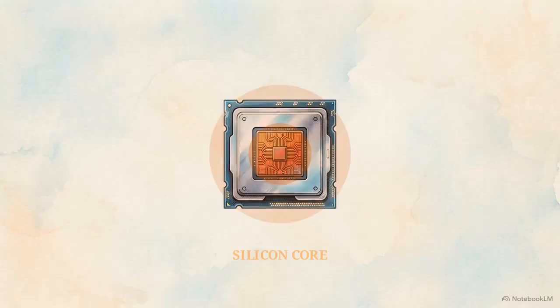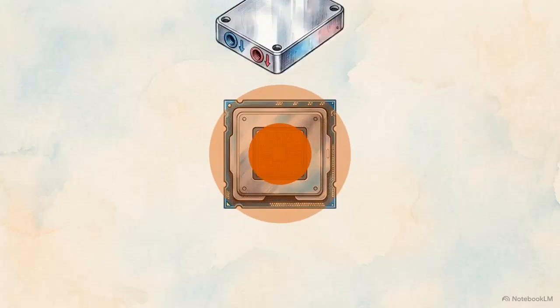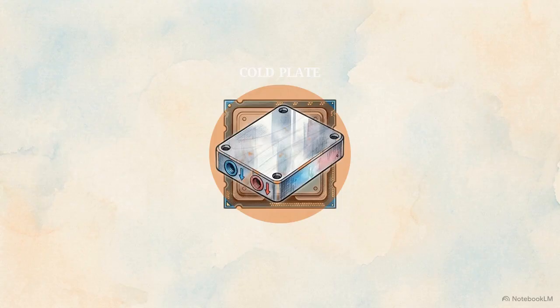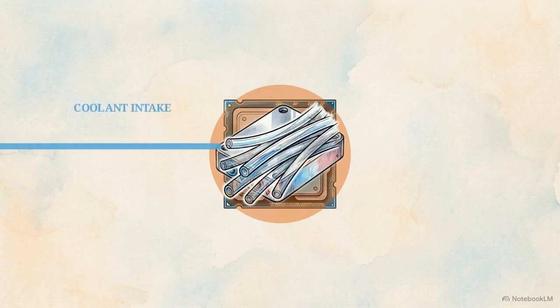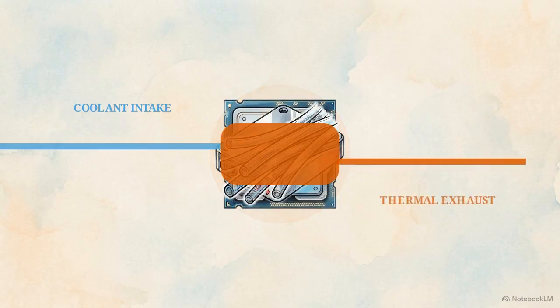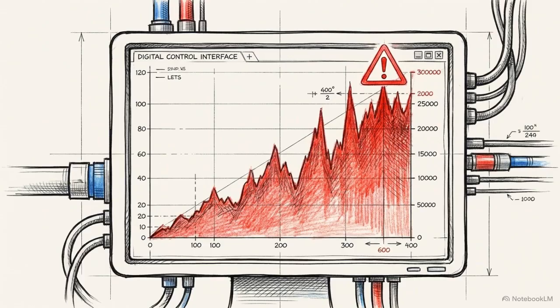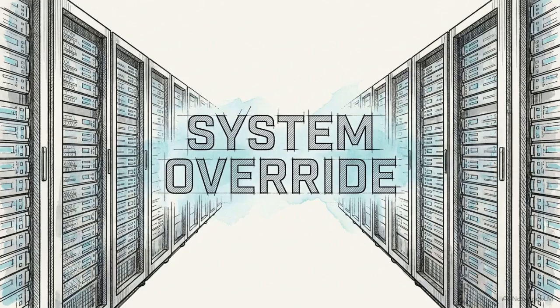Here we see a direct-to-chip setup. A specialized cold plate mounts directly onto the processor, piping microtubes of engineered coolant right over the hottest cores to pull thermal energy directly out of the silicon. With massive AI workloads, waiting for a temperature spike to happen before reacting is a mathematical gamble. Software has to take over where mechanical cooling reaches its limits.